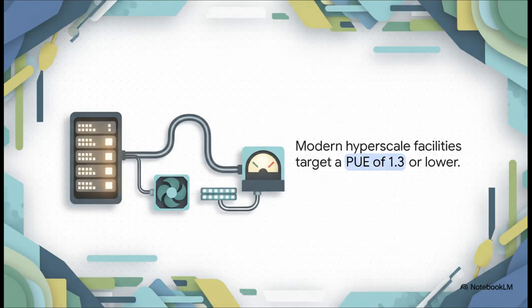A PUE of 1.3, which is the target for these modern facilities, means that for every 1.3 watts pulled from the grid, 1 full watt is powering the IT equipment. The other 0.3 watts run the cooling, lighting, and everything else. And that is a huge efficiency gain over older data centers.